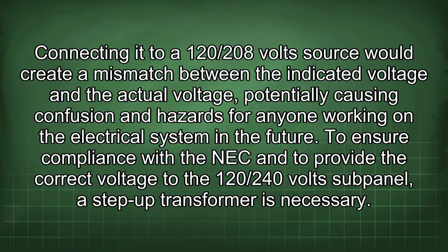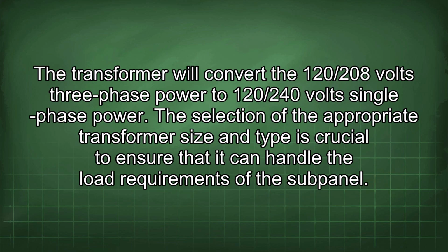To ensure compliance with the NEC and to provide the correct voltage to the 120/240 volt subpanel, a step-up transformer is necessary. The transformer will convert the 120/208 volts three-phase power to 120/240 volt single-phase power. The selection of the appropriate transformer size and type is crucial to ensure that it can handle the load requirements of the subpanel.